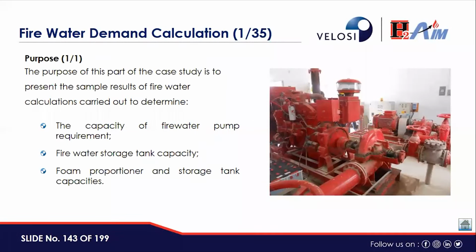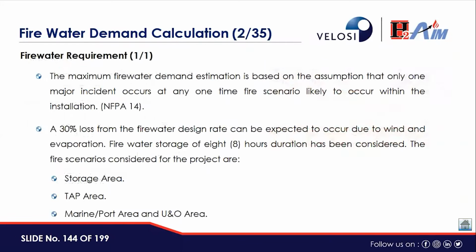The purpose of this part of the case study is to present the sample results of the fire water calculations carried out to determine the capacity of fire water pump requirement, fire water storage tank capacity, foam proportioner and storage tank capacities. So for fire water requirements, the maximum fire water demand estimation is based on the assumption that only one major incident occurs at one given time, a fire scenario likely to occur within the installation as per NFPA 14. So there will not be any multiple occurrence of fire.